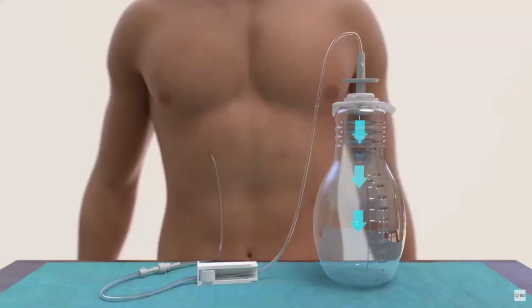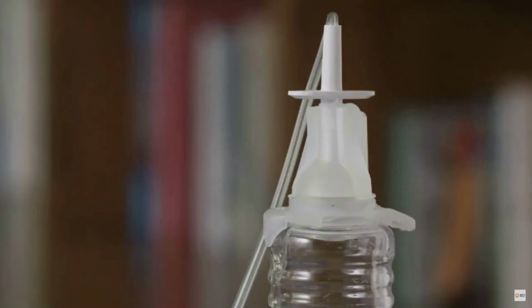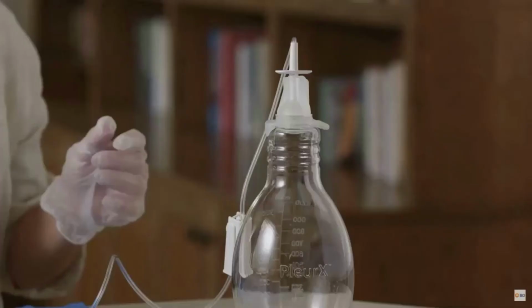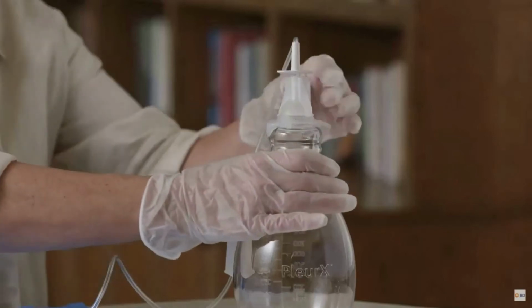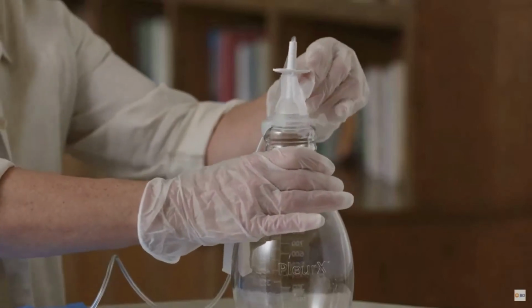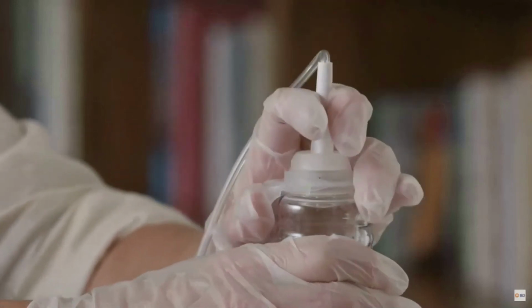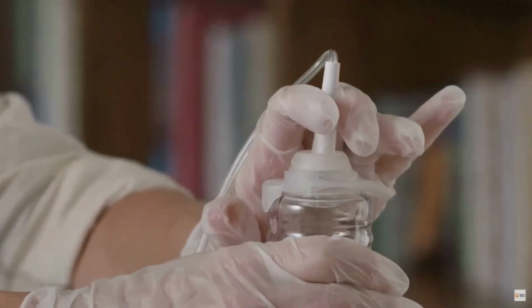PleurX drainage bottles use active vacuum technology that provides suction to automatically drain the fluid. The support clip on the drainage bottle maintains the foil vacuum seal until you're ready to break it. To open the seal, steady the bottle with one hand and remove the support clip with the other hand. Hold and push the white T-plunger straight down to puncture the foil seal.